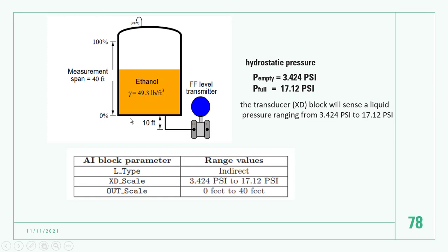For example, a tank pressure transmitter, hydrostatic pressure. Hydrostatic pressure is 3.424 psi. Therefore, here 100% is 17.12 psi. How did we get this number? In the future we will talk about calibration. We will talk about how to calculate this. Okay.